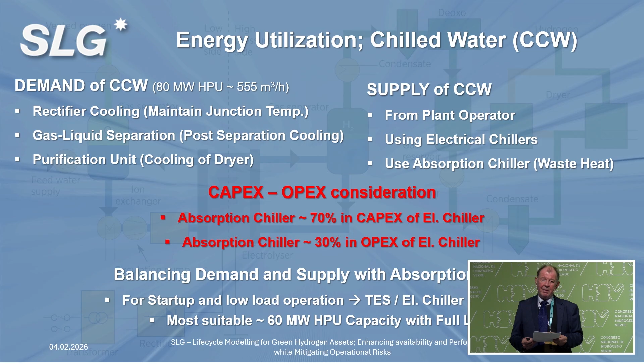By contrast, if you use a waste heat-driven absorption chiller, it delivers much better economic performance. CapEx, we only use about 70%. Operation costs go down to 30% compared to an electrical chiller. Of course, for operational reasons, you may need a small electrical chiller for startup.